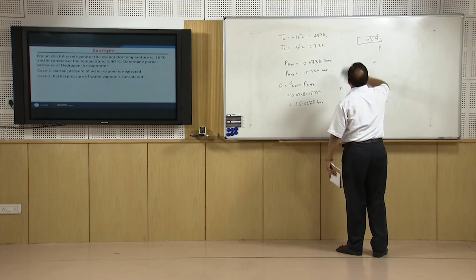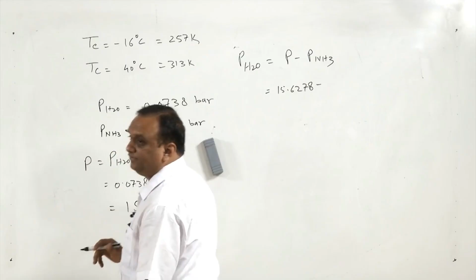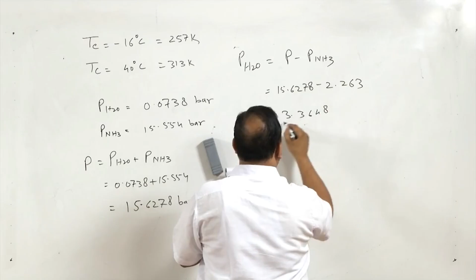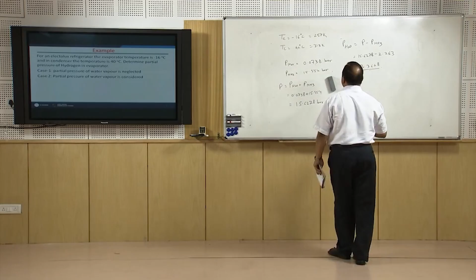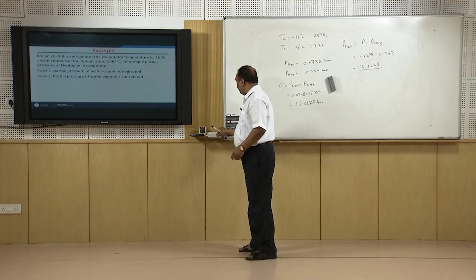Now, with this total pressure, if I remove the pressure of ammonia, I will get the pressure of hydrogen. So, the pressure of hydrogen is equal to the total system pressure minus the partial pressure of ammonia. The total pressure is 15.6278 minus the partial pressure of ammonia at minus 16 degrees centigrade, which is 2.263, and that gives the partial pressure of hydrogen as 13.3648 bar. So, with the presence of traces of water in the system, the partial pressure of hydrogen in the evaporator has slightly increased.